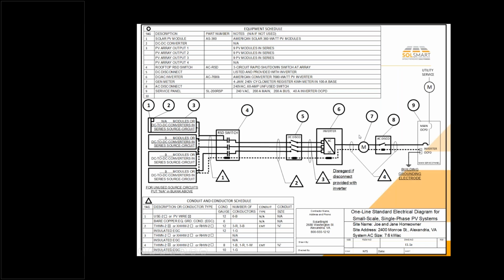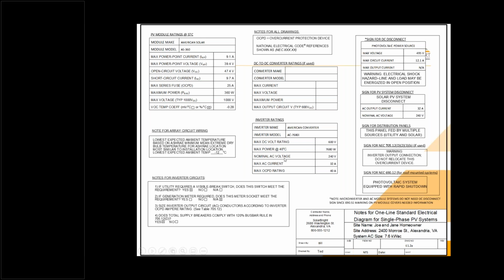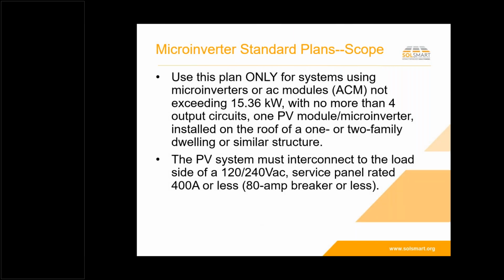We might have a meter that the utility wants to see on the system, but it also may be a meter just for the owner as well, or for both. And we're in compliance, and we meet the 120% bus bar rule, so we're good to go. So that's the first example.